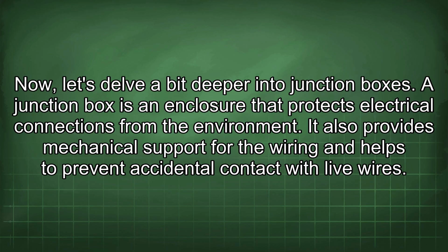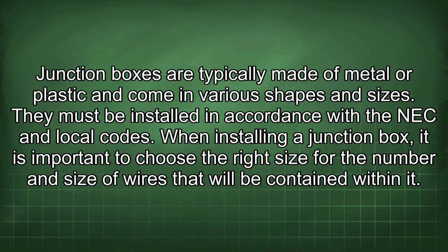Now let's delve a bit deeper into junction boxes. A junction box is an enclosure that protects electrical connections from the environment. It also provides mechanical support for the wiring and helps to prevent accidental contact with live wires. Junction boxes are typically made of metal or plastic and come in various shapes and sizes. They must be installed in accordance with the NEC and local codes.